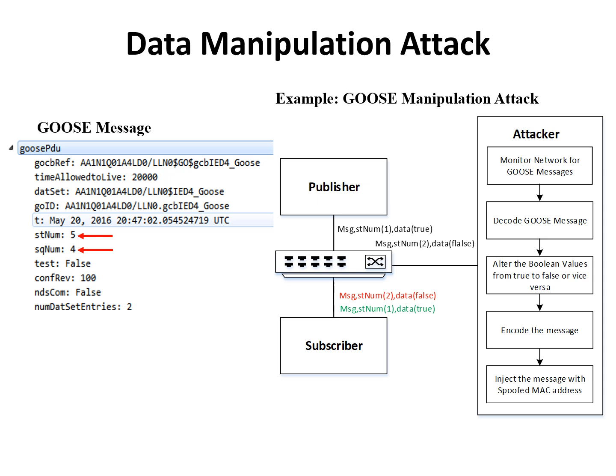The Goose protocol is vulnerable to different types of attacks, such as data manipulation and goose poisoning attacks. In the data manipulation attack, the attacker sniffs the network communication waiting for goose message transmission. Since the goose message data is not encrypted, the attacker can receive and decode the data field to find out the data structure used by the IED. Once the data structure is known to the attacker, he can construct a new message with manipulated data and transmit it with a new status number. All subscribers will receive the message and process.